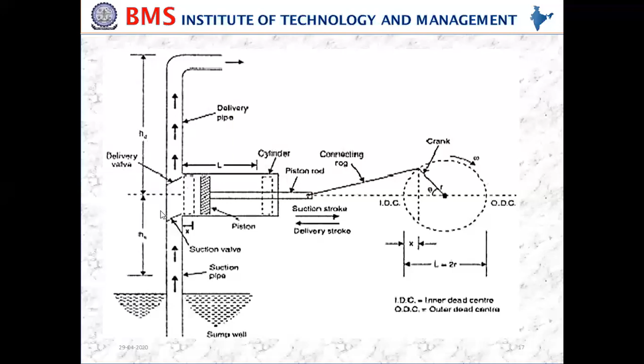And what is priming and cavitation? Priming is the process of filling up the suction pipe. In the case of a centrifugal pump, priming is the first process which you need to do, right? So priming is the process of filling up the suction pipe, the impeller casing, and the delivery pipe up to the valve, with the fluid to be pumped.